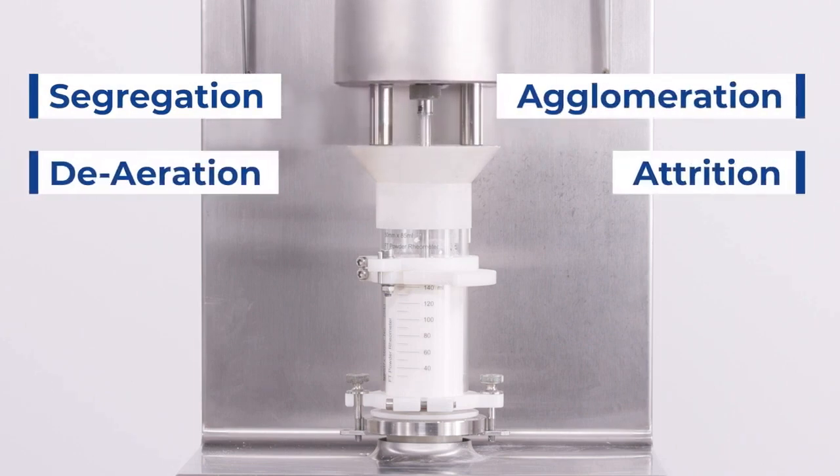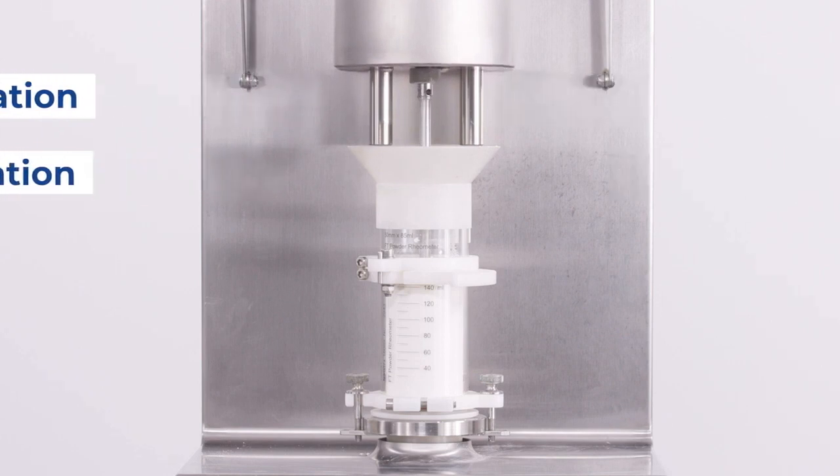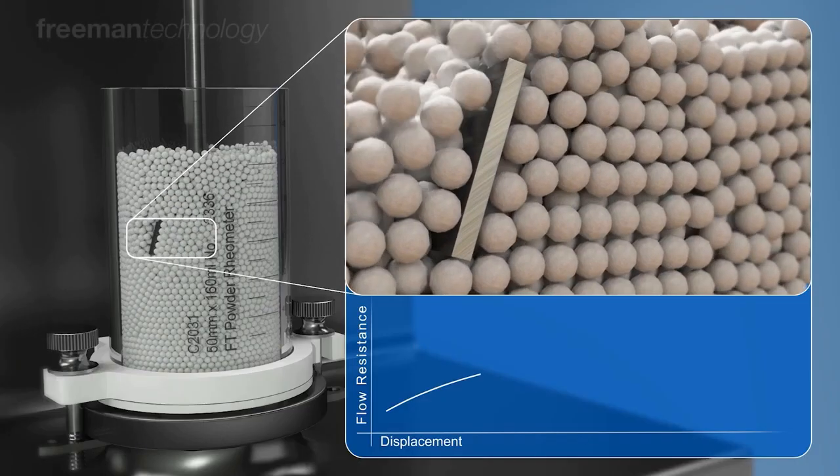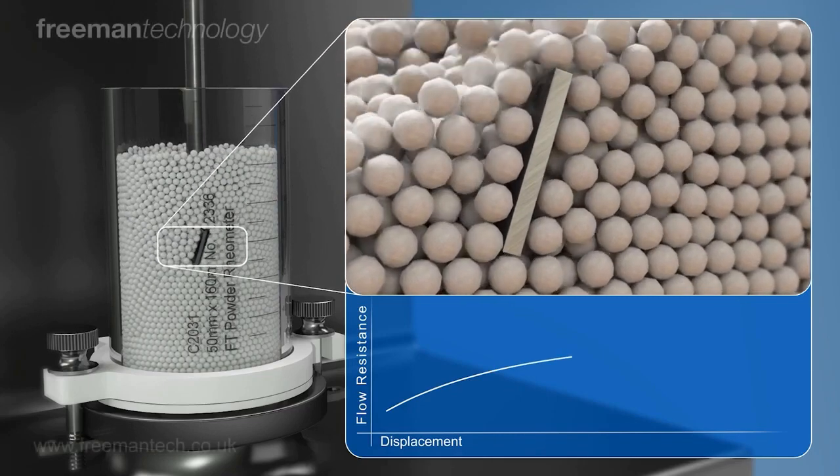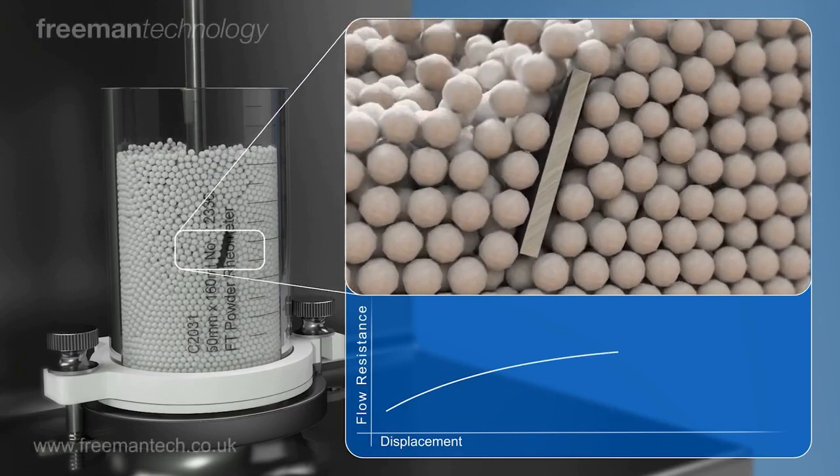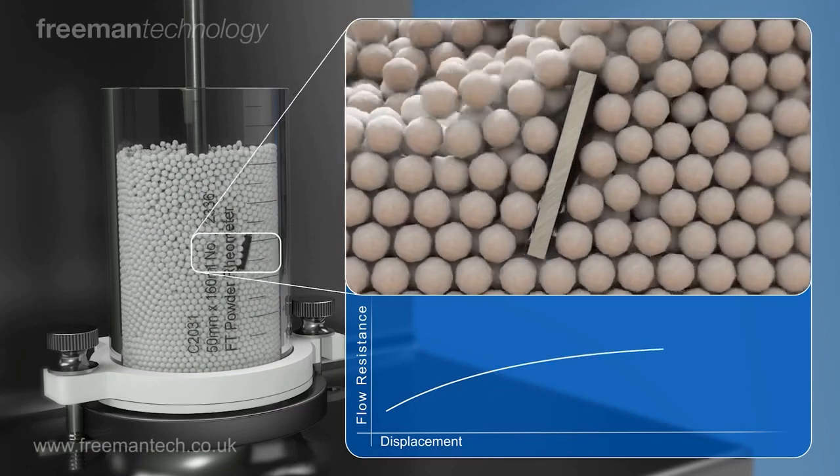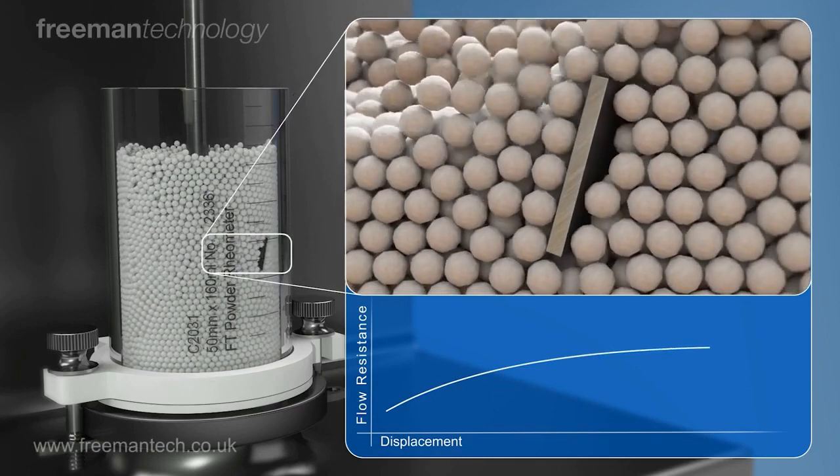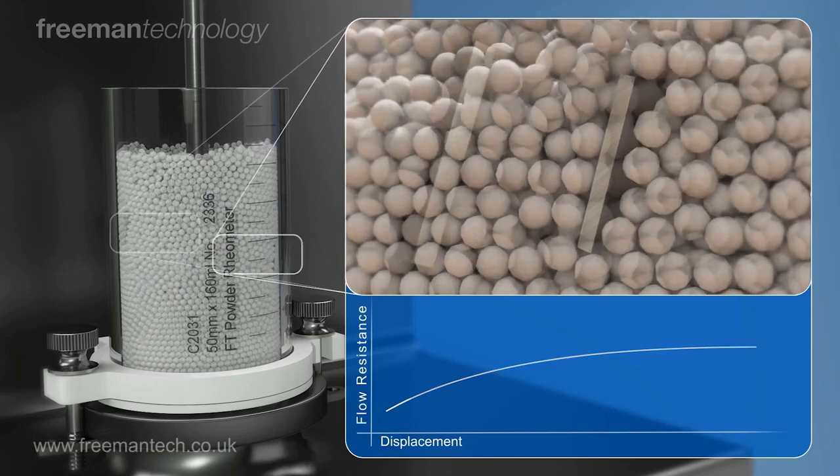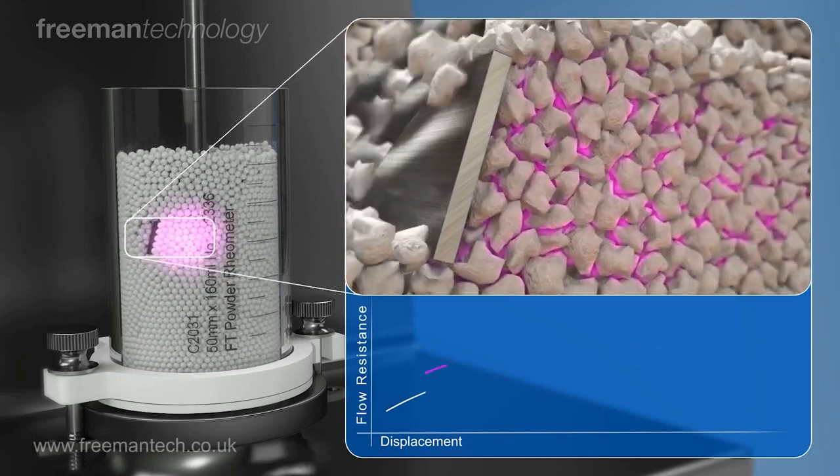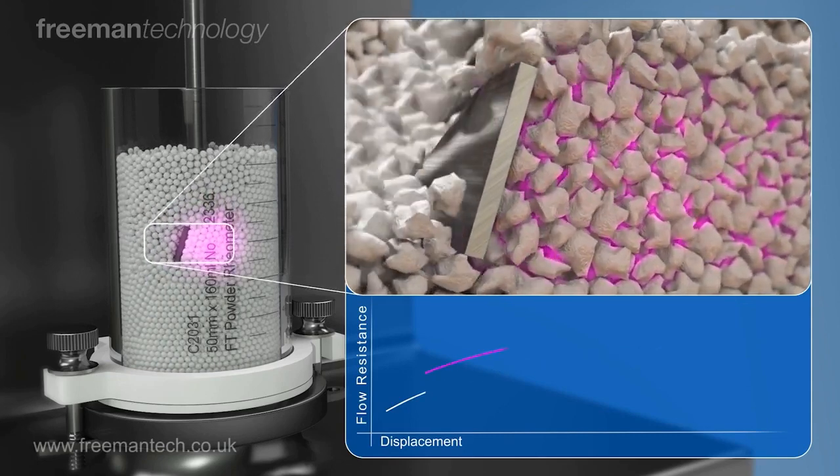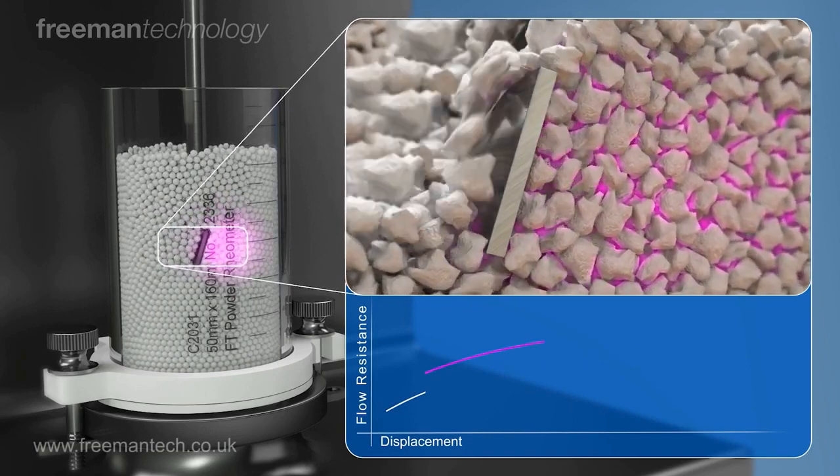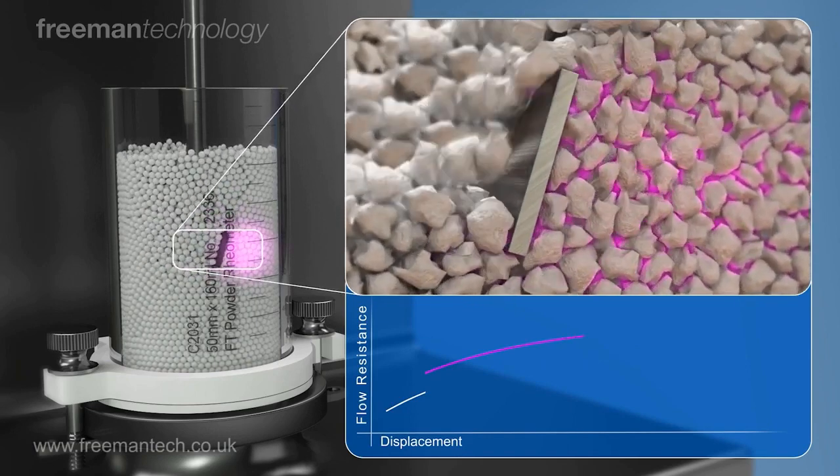The main flow parameter that we gather from this experiment is the basic flow energy. This characterizes the powder's resistance to the blade's downward traversal under a set path at a fixed tip speed, which then implies the powder's resistance to flow within a constrained environment. Another parameter that we can gather from this experiment is the powder's specific energy. This is the resistance of the blade's upward traversal through the powder bed and thus reflects the powder's flowability in an unconfined space.